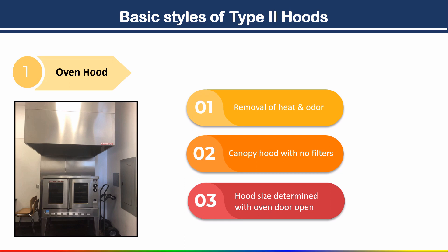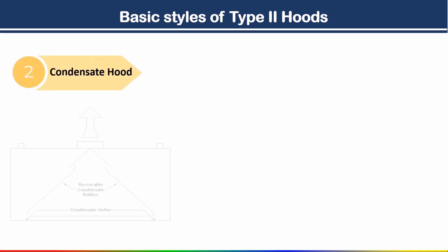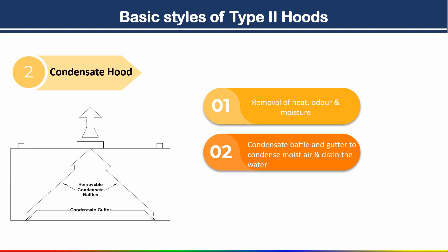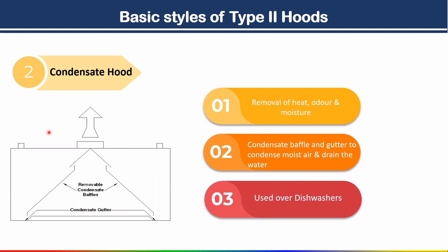Hood size for the oven hood is determined by the oven door size. When you open the door of your oven, you have to give 6 to 12 inches of overhang beyond the door for the hood. The second type 2 hood is the condensate hood. This type is used for removal of heat, odor and moisture. It generally uses a condensate baffle and gutter — the condensate gutter condenses moist air and drains the water. This type is generally used over dishwashers, steam tables, etc.